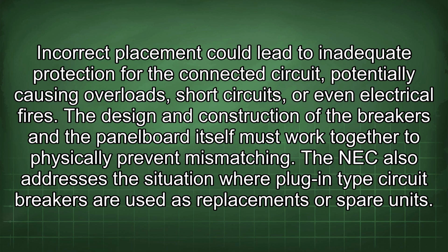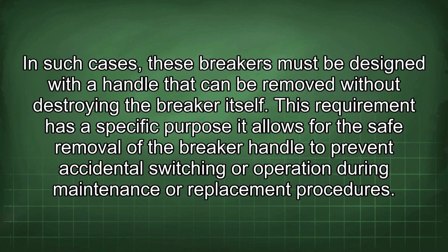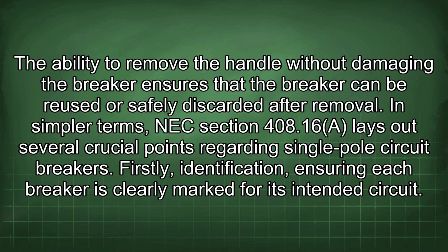The NEC also addresses the situation where plug-in type circuit breakers are used as replacements or spare units. In such cases, these breakers must be designed with a handle that can be removed without destroying the breaker itself. This requirement has a specific purpose. It allows for the safe removal of the breaker handle to prevent accidental switching or operation during maintenance or replacement procedures.